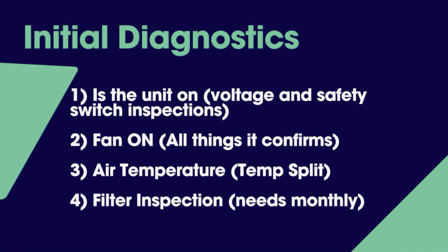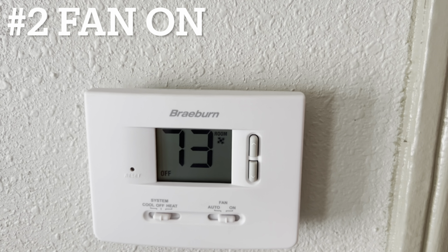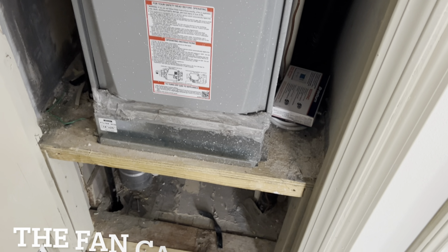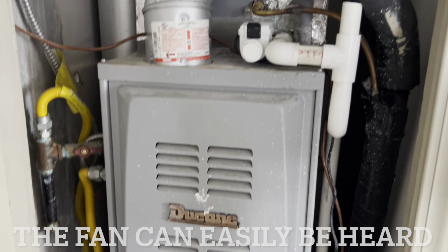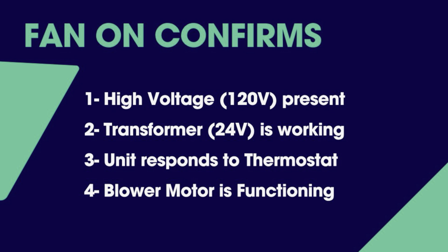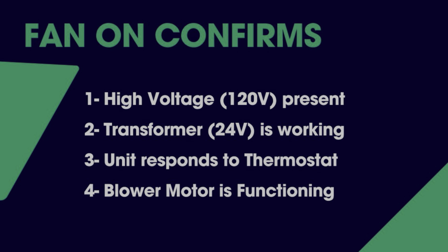Next step in diagnostics is fan on. Simply go to the thermostat, put it on the fan on setting, and immediately the fan should respond. Within 10 seconds, you can find out 4 things: that you have high voltage, low voltage, the unit is responding to the thermostat, and your blower motor is functioning.